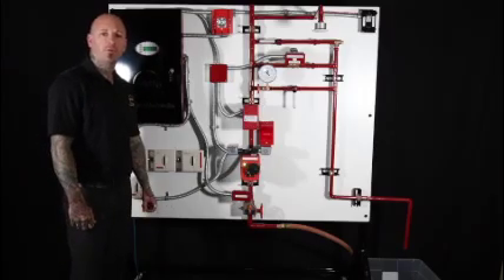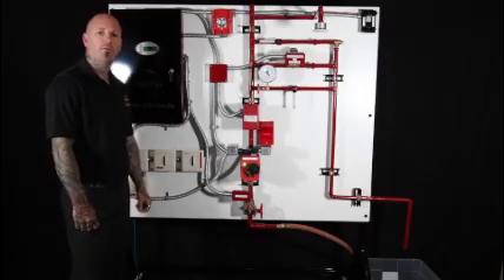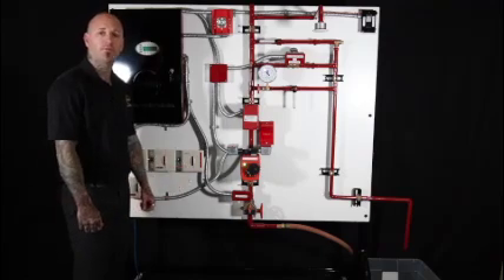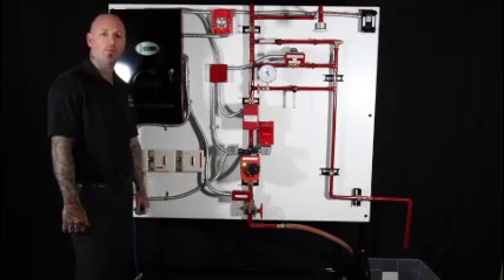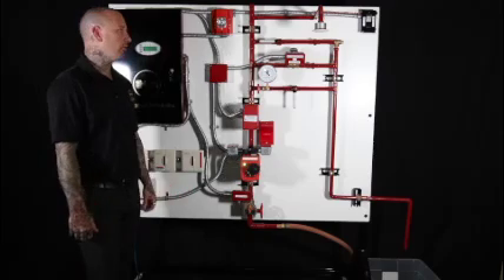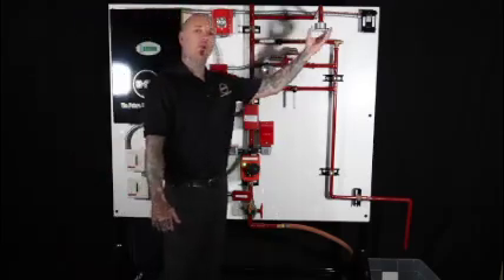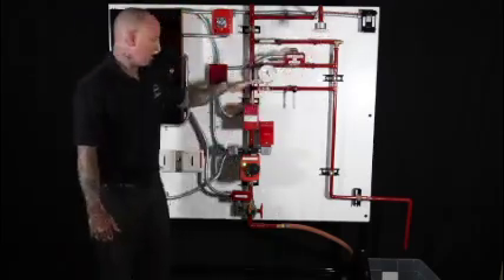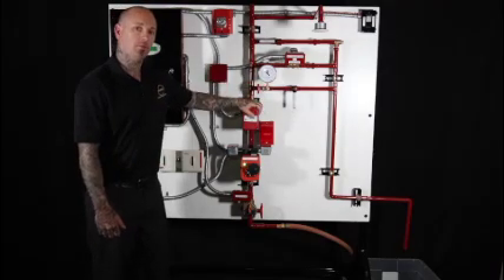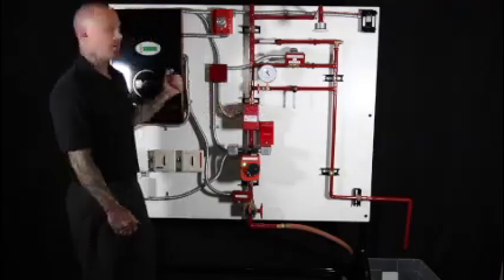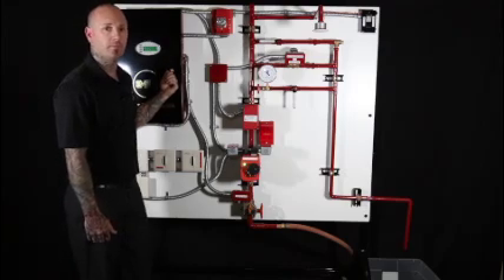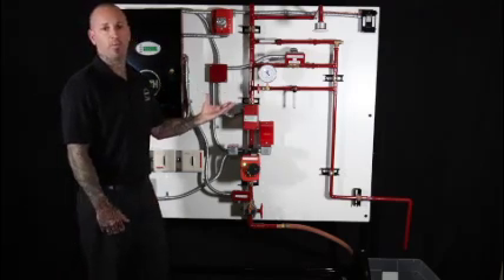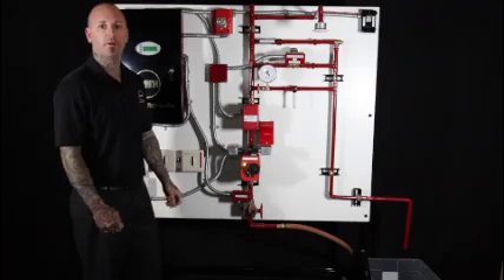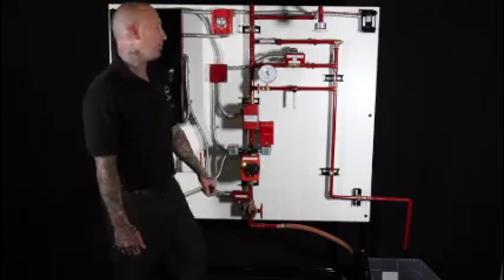Now that I've shown you some of the components used here in our system, I like to run the system through its first scenario. Scenario 1, normal operation. Normal operation, you have a sprinkler head going off and you have a flow switch monitoring the flow of the water, sending alarm signals to the panel. The system will work in normal operation and continue to fight the fire as designed. Here's how that works.